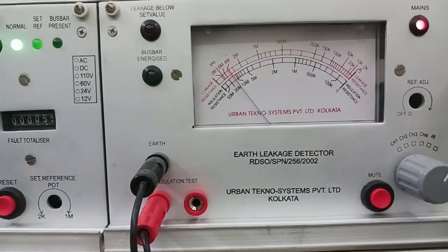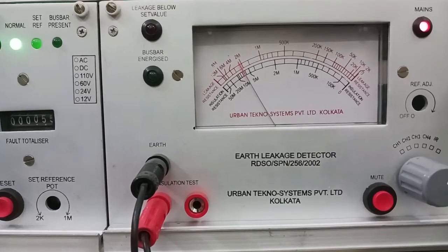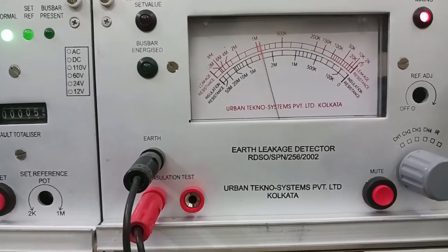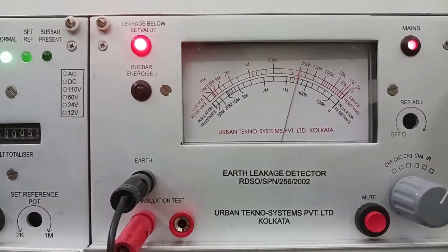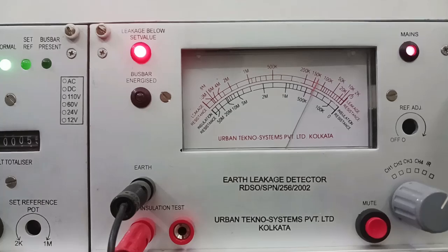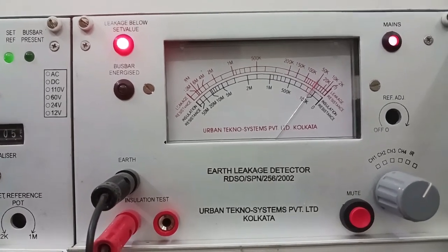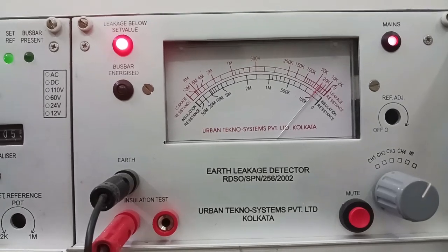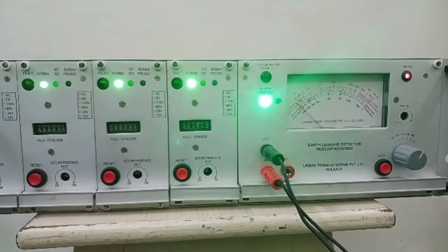scale of the meter. The factory set minimum insulation resistance value is 1.5 megaohms and the corresponding LED will glow if insulation resistance is found to be lower than the set value. This insulation resistance measurement is only possible if the test points are unpowered. However, if any powered points are connected to the IR inputs, the bus bar energized LED will glow and the system will be automatically disconnected through internal circuitry.